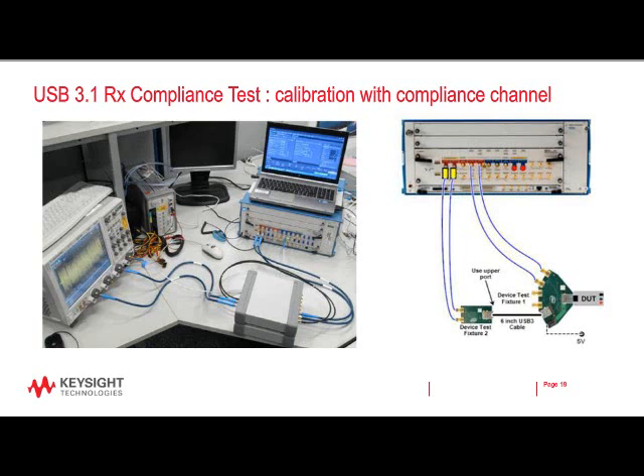On the right-hand side is a test fixture with a DUT hooked into it. You see the pattern generator, the two cables on the left, stimulating the DUT, and then there's a loopback path. Those are two cables on the right-hand side going back to the test instrument for error detection.